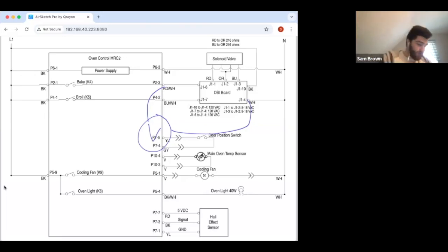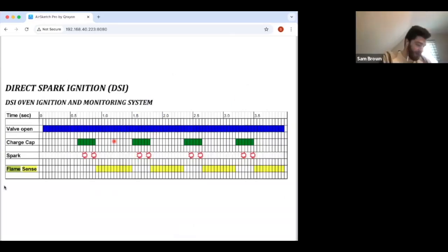Well, the reason we know the DSI board and the flame recognition are both working is because we have this information on the cycle. We know it's actually a pretty short cycle. It only tries for 4 seconds, and if it doesn't establish a flame, it will stop, try again, stop, try again. We had it running for 20 to 30 seconds, so it was able to establish a flame, and the DSI board was able to tell that the flame has been established.